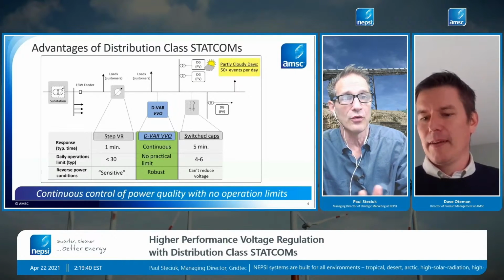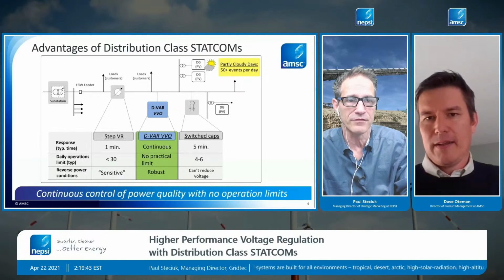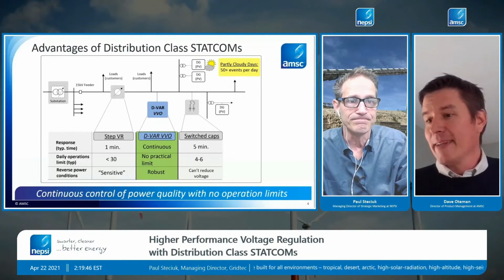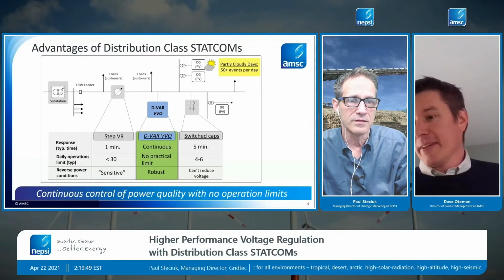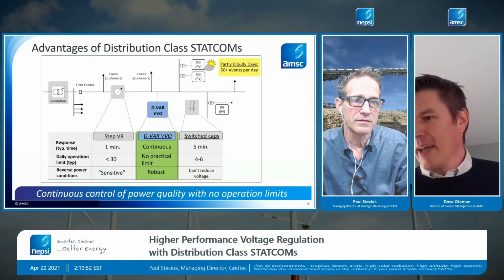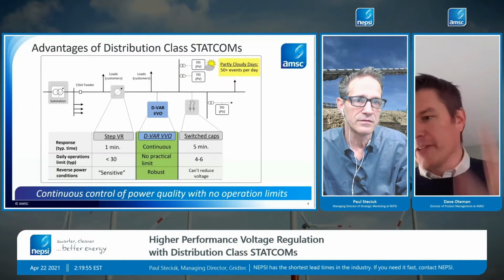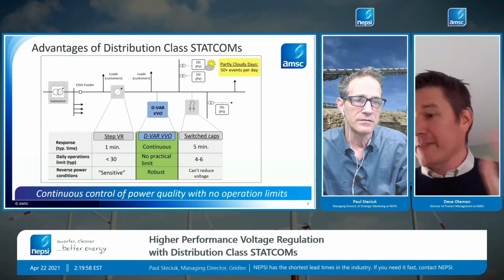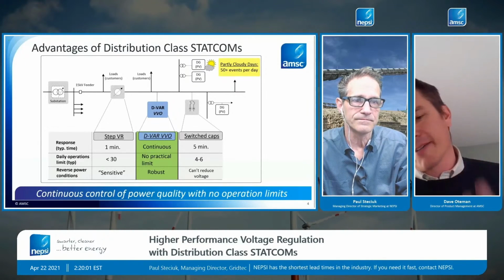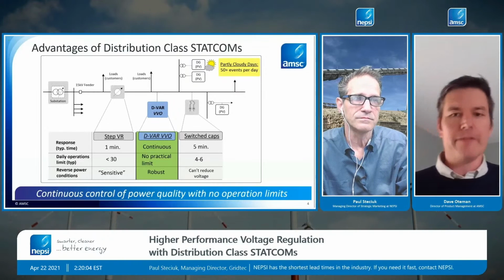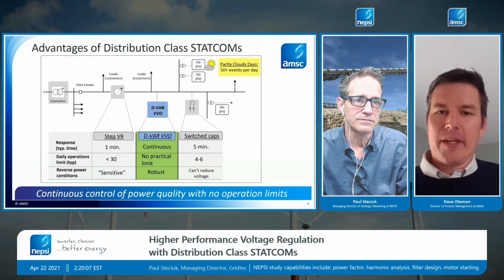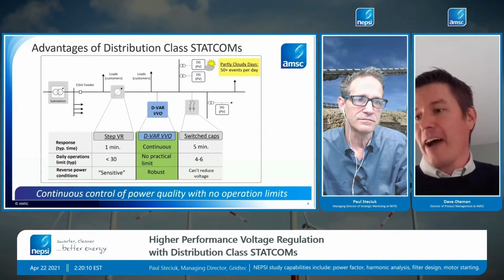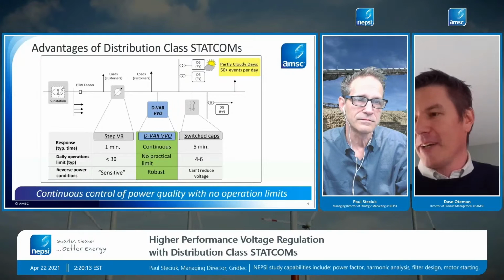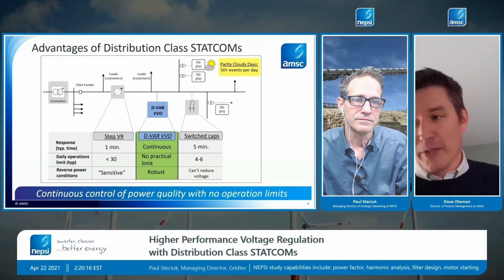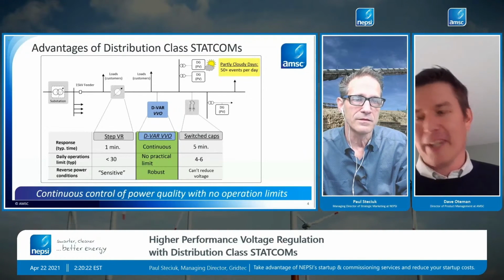So interesting. There's no limitation on the number of times this VVO switches, correct? There is not, and with this application, the asset managers at utilities love the fact that whether I'm on this circuit or that circuit, the lifetime is basically constant. Asset planners plan on a 20-year lifetime from the D-VAR VVO STATCOM, as opposed to, you might get 25 years of life on a slow circuit with a line regulator, but on a high renewable circuit, you might get 2 years. We have customers coming to us with 2.5-year failure modes on their line regulation exactly for that reason.